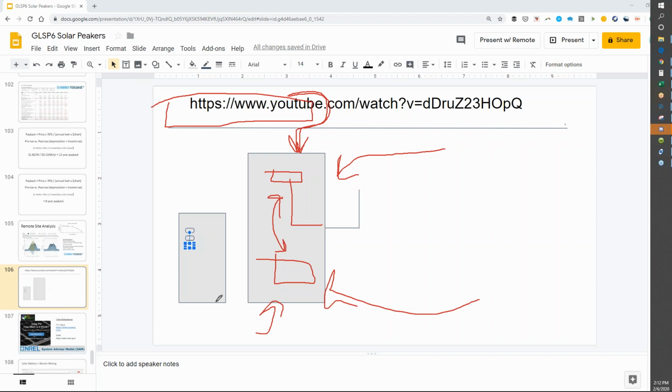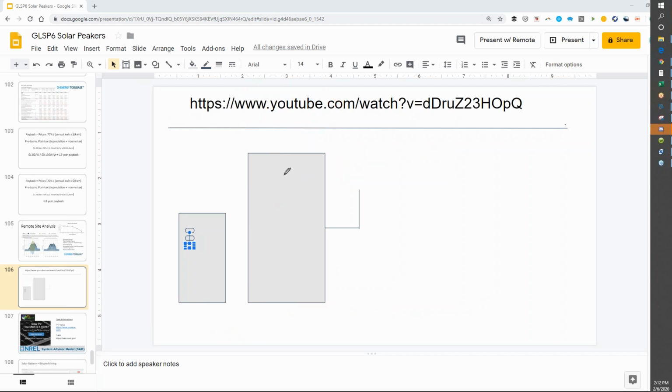And it could be very tempting, if this power is coming through the bottom of the panel up here and the top of the panel up here, to land the solar array on the top and the utility on the bottom. But that's actually a mistake. On an electric service panel, the utility feed, the feed that is always live, the feed that is always hot, is going into the top. And then the disconnected load, when solar loses that utility connection, it disconnects. That feeds into the bottom.